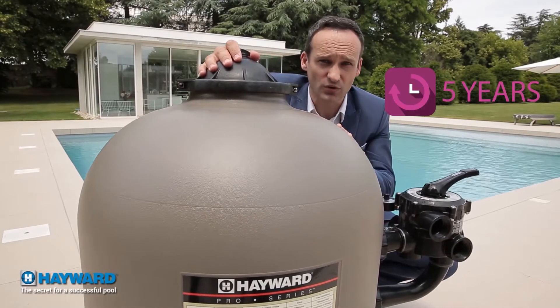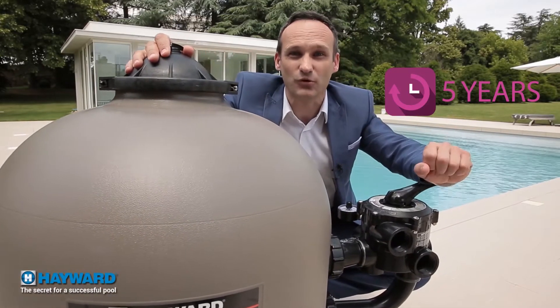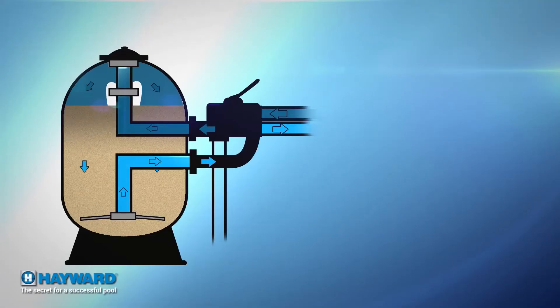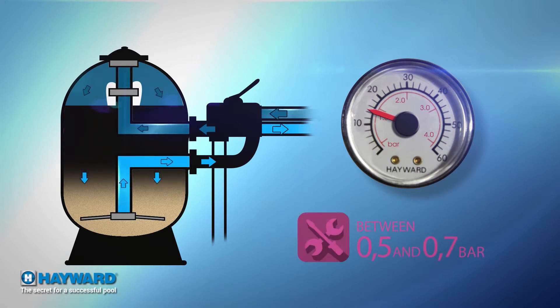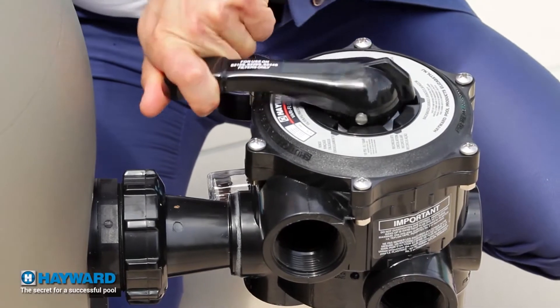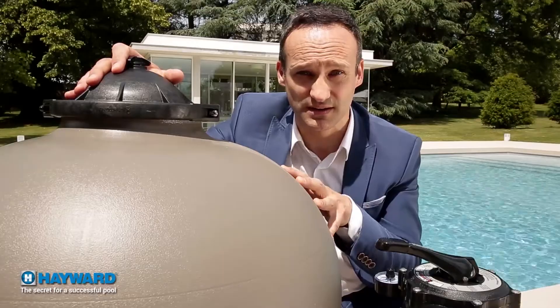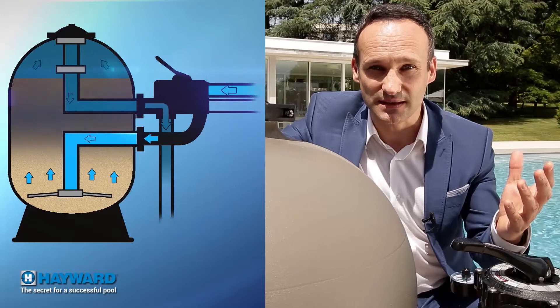Besides replacing the sand every five years or so, standard sand filter maintenance involves a backwash, which is rather costly in pool water. As the filter clogs, pressure increases — visible on the pressure gauge. When pressure rises 0.5 to 0.7 bars above normal, a backwash is needed. Backwashing reverses the direction of water flow to dislodge debris trapped in the sand. The pool water enters the filter, lifts and cleans the sand, then goes directly to the drains.